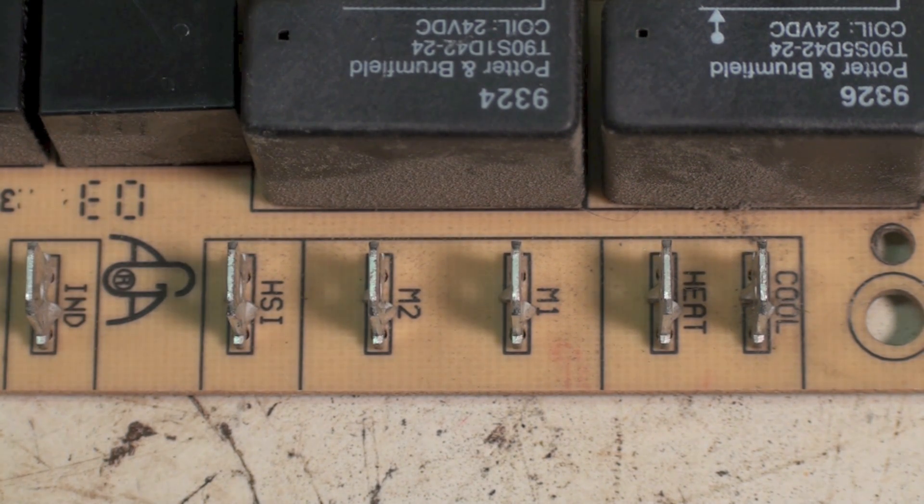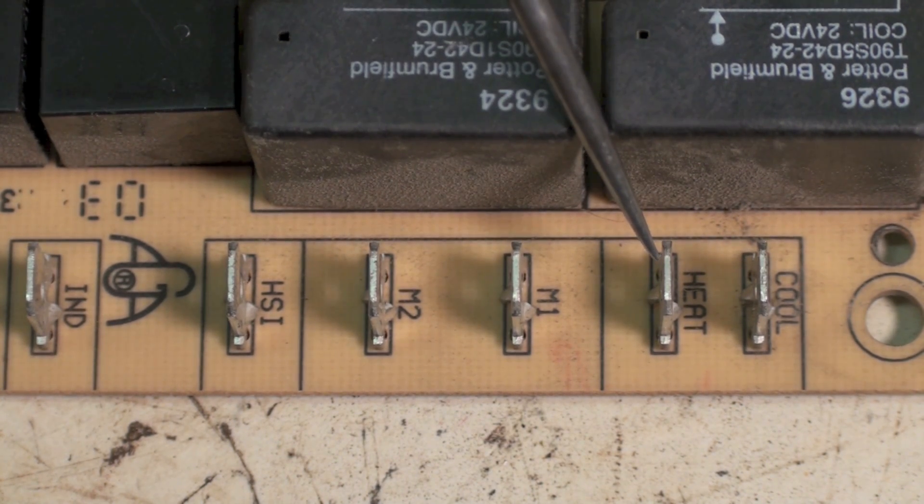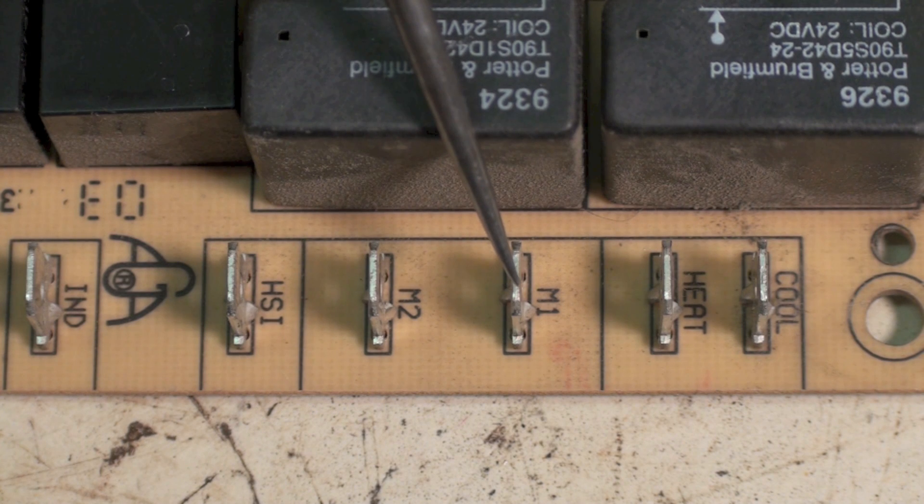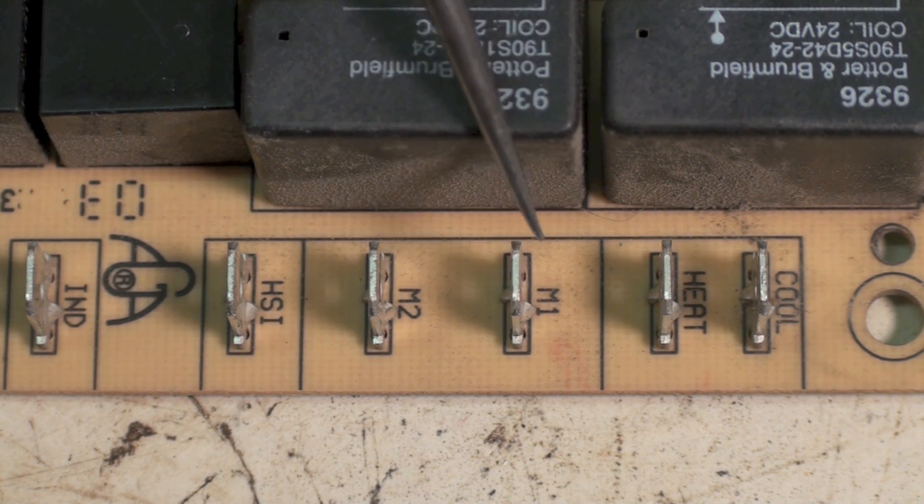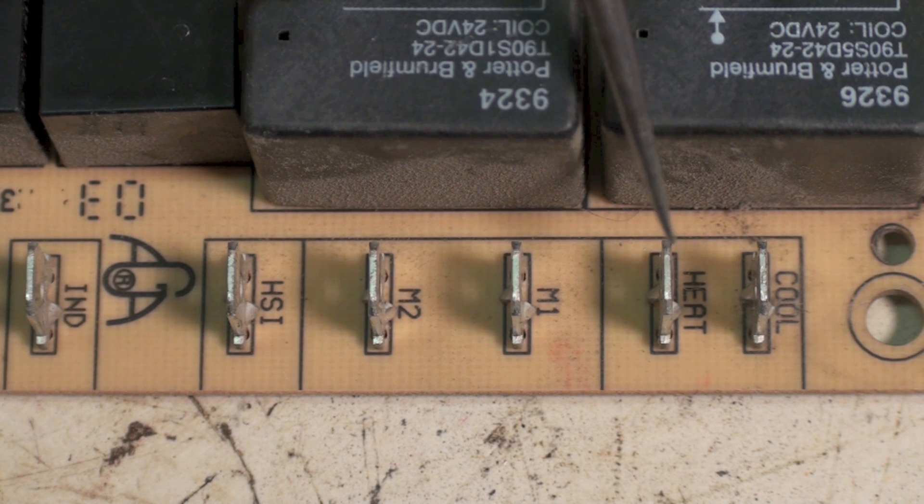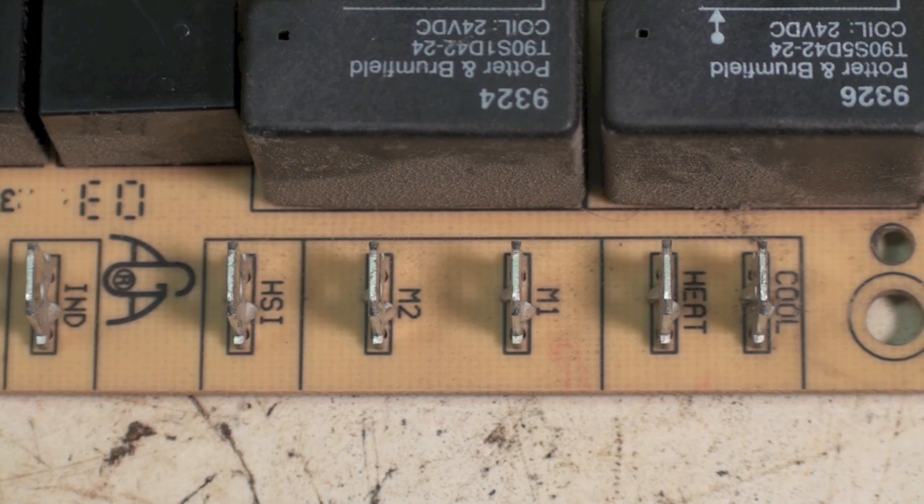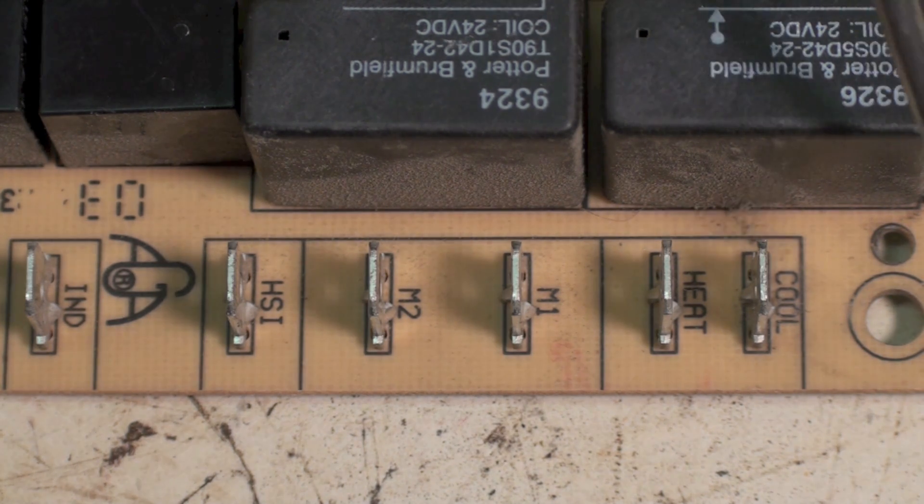If I had, say, red on heat and I had blue on M1, then I could take the blue from M1 and put it where the red is, and then put the red on M1. You can do that - that's okay. You haven't messed with your common, you haven't put two speeds together or anything like that. The heat and cool speeds are separated by a relay so it'll work fine.